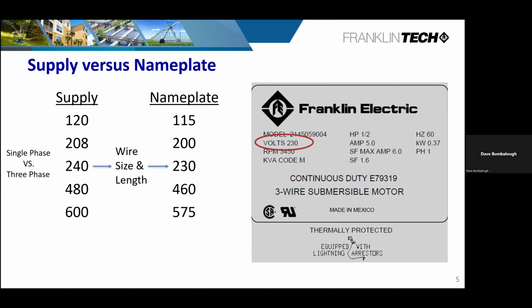What I like to point out is that the Department of Energy is basically the governing and regulatory body that most power companies have to answer to. As a manufacturer, we get our information from them, especially if you're trying to build a piece of equipment to run on what's being provided. So in the early days, 120, 208, 240, 480, and 600 volts were our nominal voltages, and the power companies were pretty consistent with keeping that right on target.